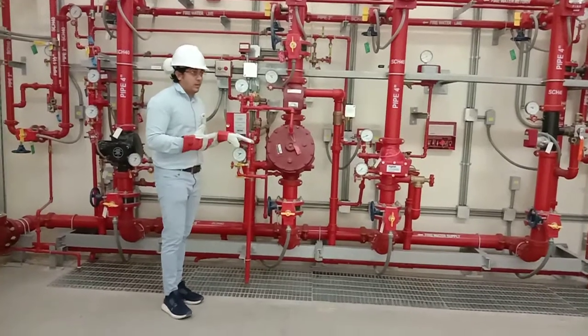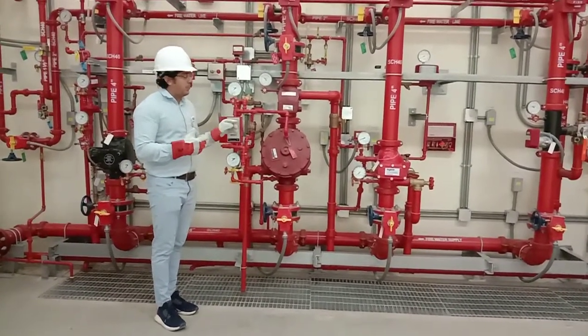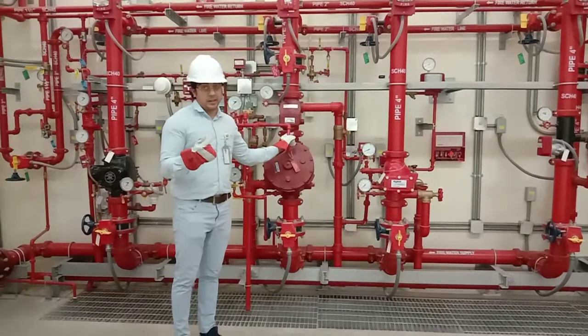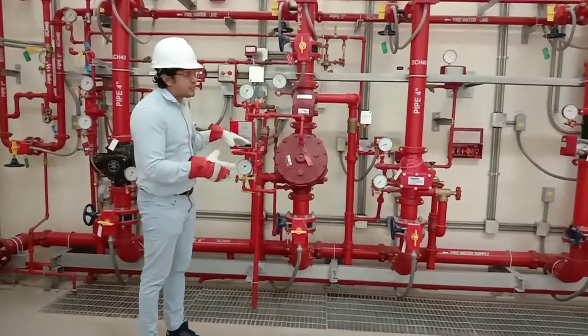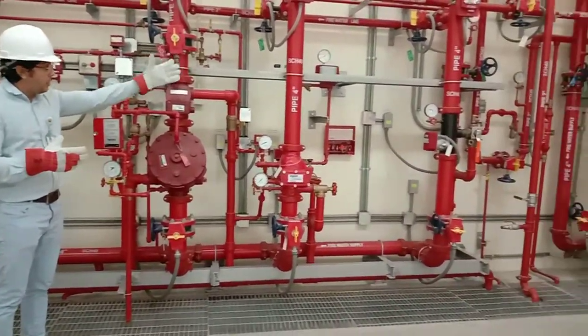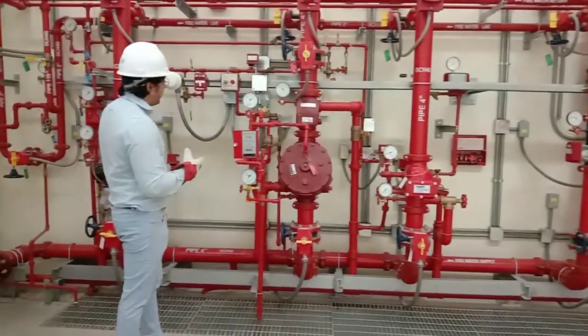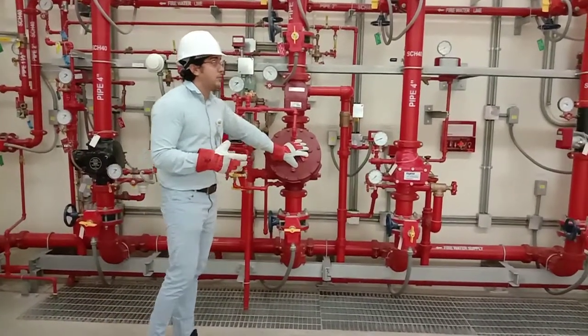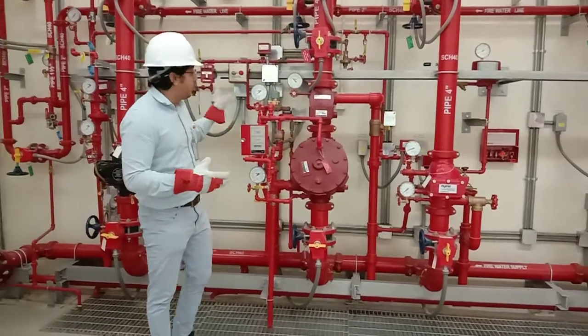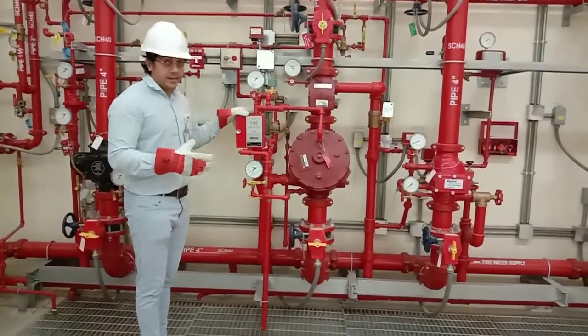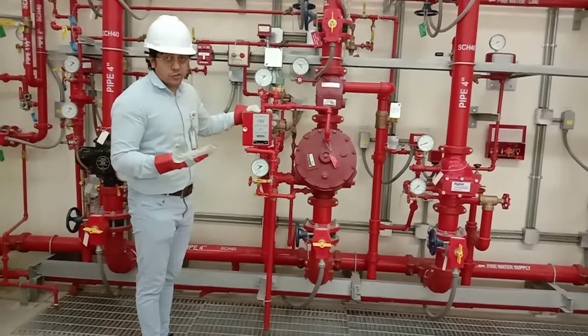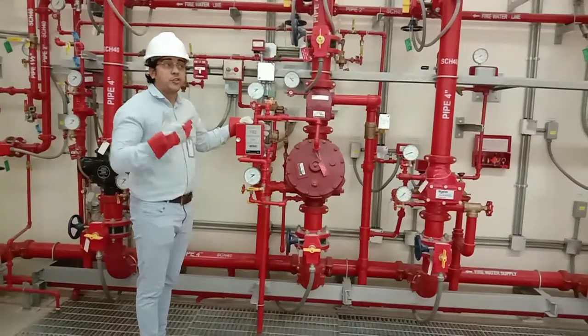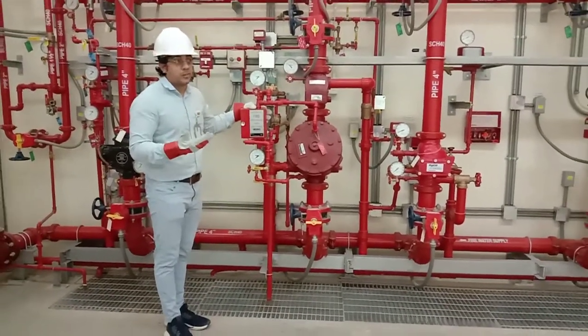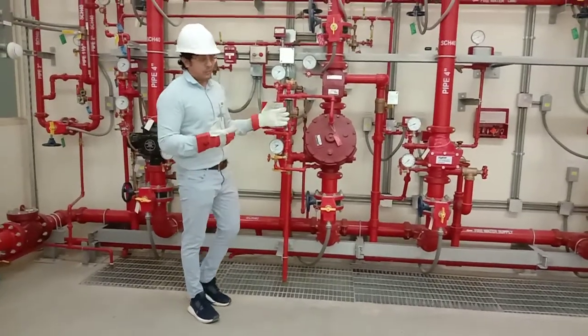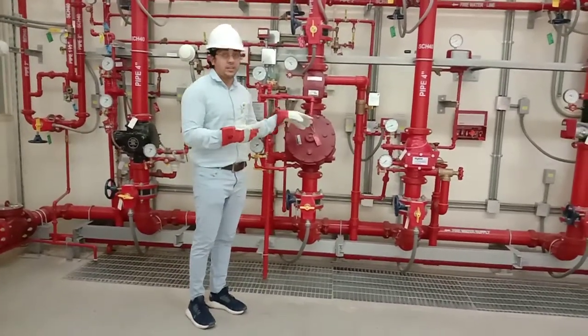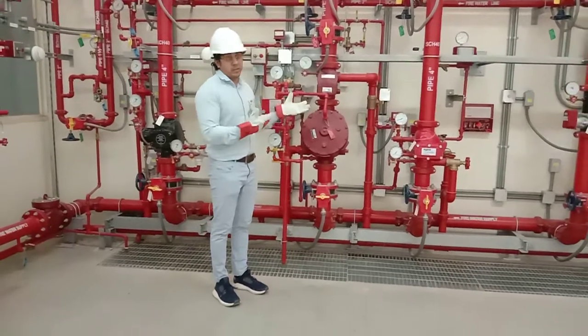This is the least installed system worldwide. The application of this kind of system is very limited. It's very complex. If you look at the wet pipe system, dry pipe system, and deluge system, and the last one, the double interlock system, this is the most complex, most advanced, most protected one, and the cost of installation will be higher. The installation, testing, and maintenance cost will be higher. We need a lot of people to maintain it. This kind of device cannot be easily maintained by some normal technician.